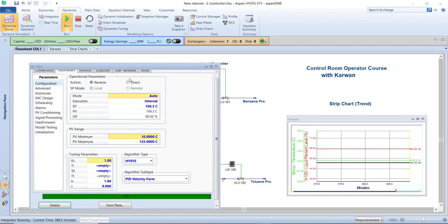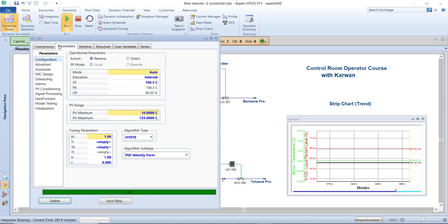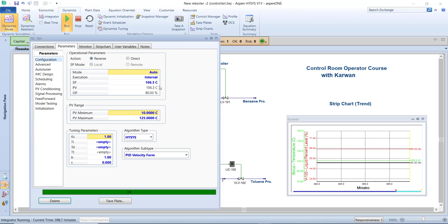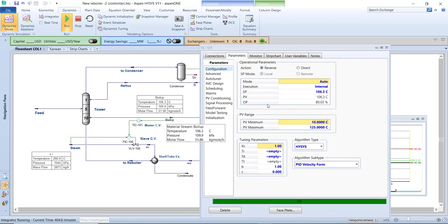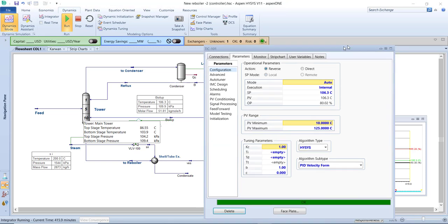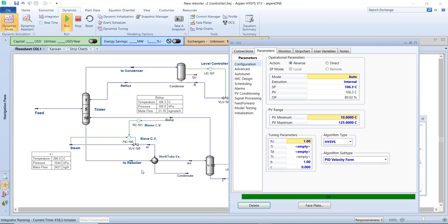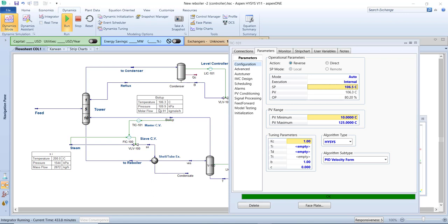I want to run the plant like a real situation. The operator creates displays in the control room to monitor the plant. We have several trends: the black one is the top condenser level, the red one is the separator level at the bottom of the tower, and the green one is the boil-up temperature. In the TIC parameter section, the setpoint is 106.3°C and the process variable (PV) is also 106.3°C — perfect, with no difference between setpoint and PV.